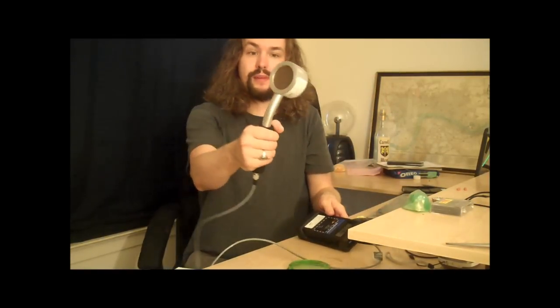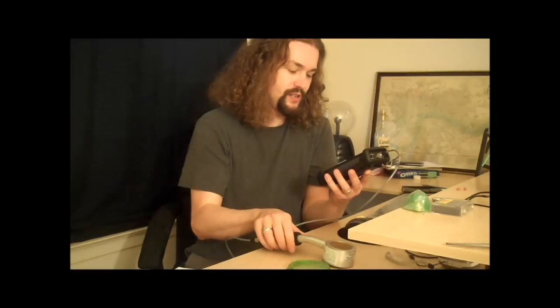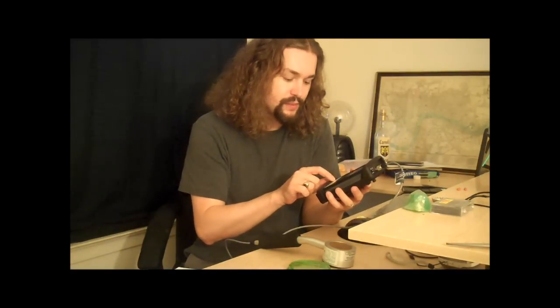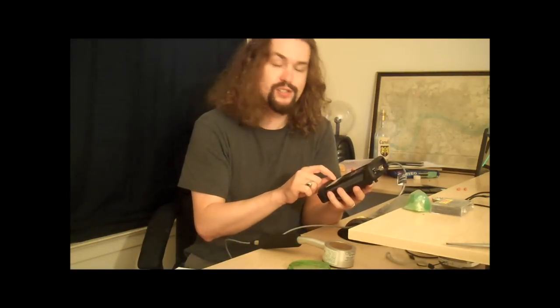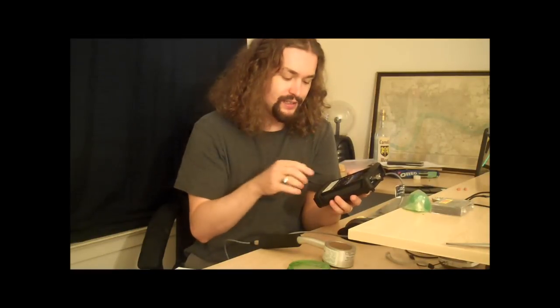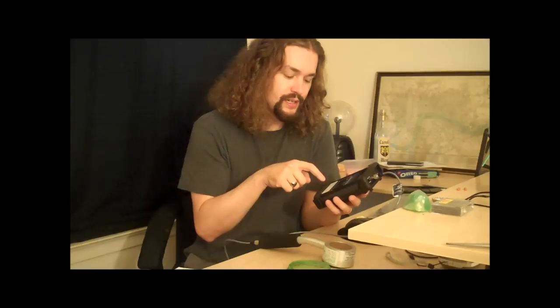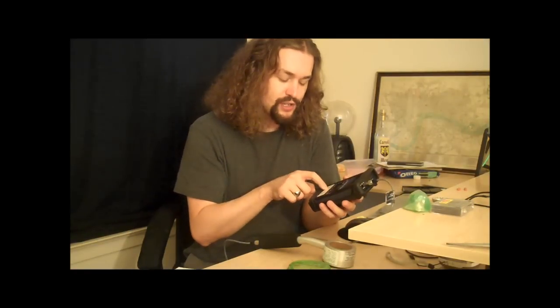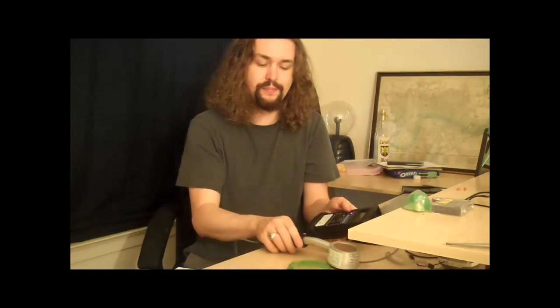First off, they calibrated my unit and both of these here. As you can see, there are little stickers that say what the calibration settings were—the reading at 50 millirems per hour. Actually, it's not millirems, it's milliroentgens. I know they're approximately the same but not technically. So 50 milliroentgens, 5 milliroentgens, 0.5 milliroentgens—calibration factors need to be changed, everything about them.